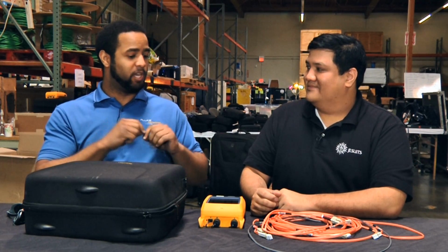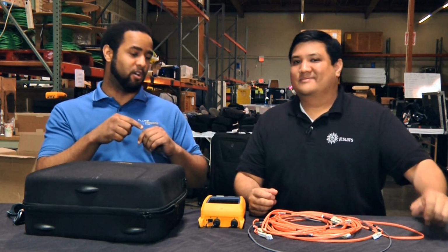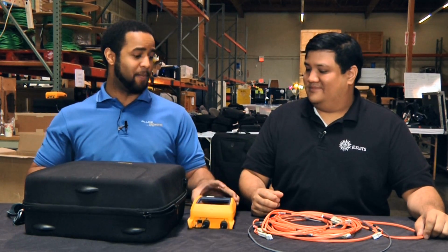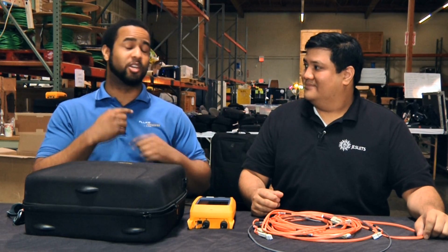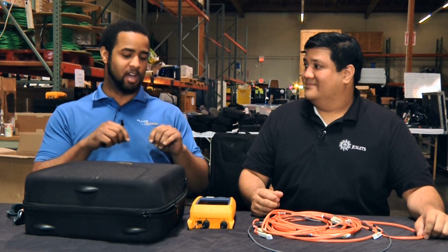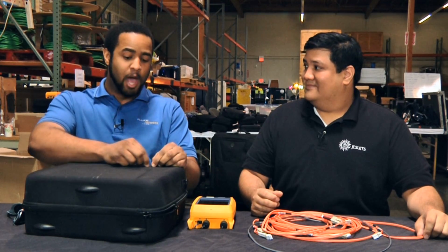What we can do is measure the distance to that fault so that you don't have to go through with a visual fault locator or a red laser and find where that light's spilling out. You can just attach your instrument, here an OTDR, and detect exactly where that break was. And you can also characterize that break. You can tell if it actually is a break, or if someone has used a fusion splicer to melt the two ends of the glass together, or a mechanical splice where they're just using a small mechanical device to hold the two together very closely.